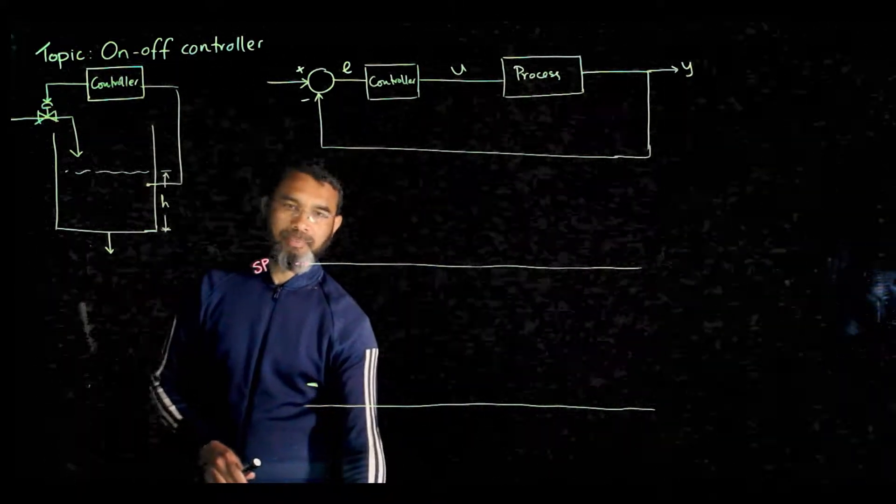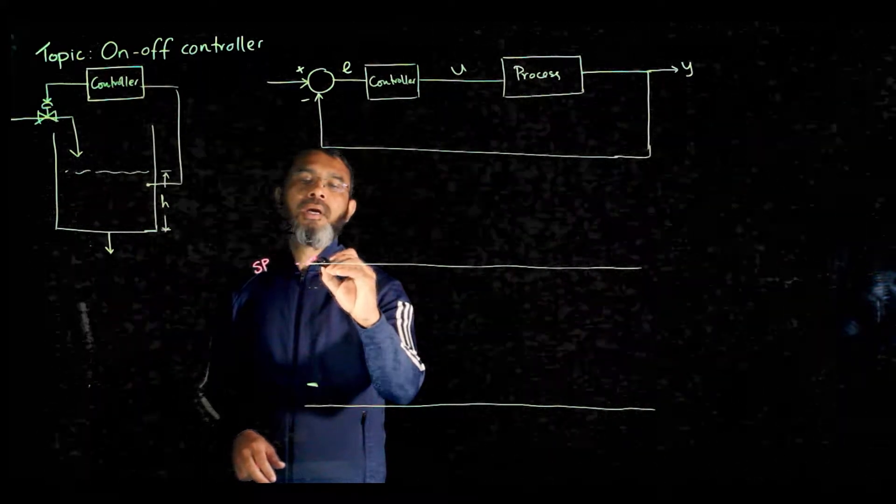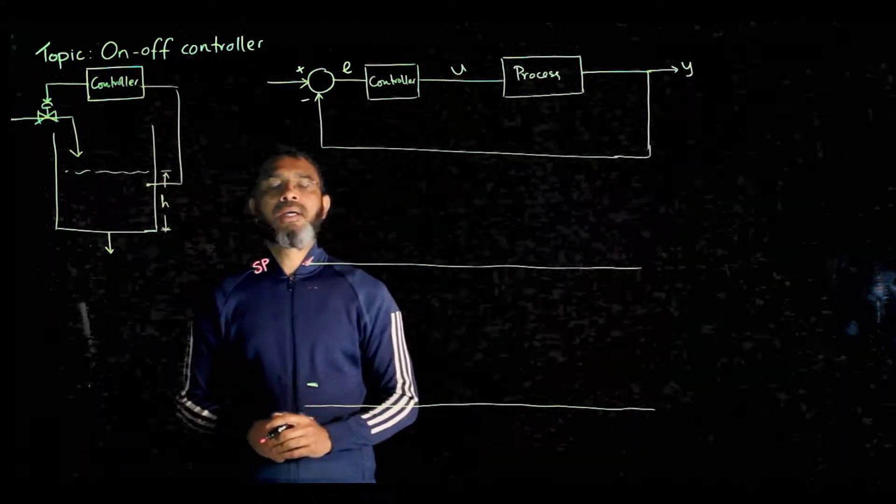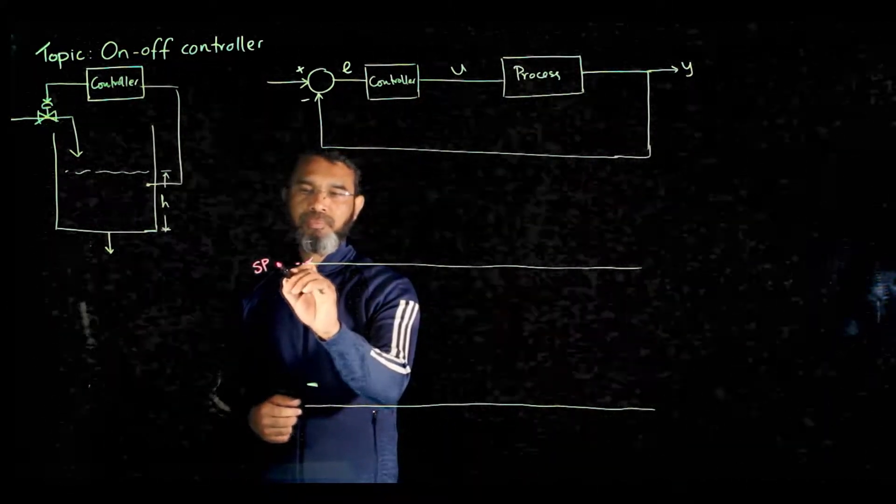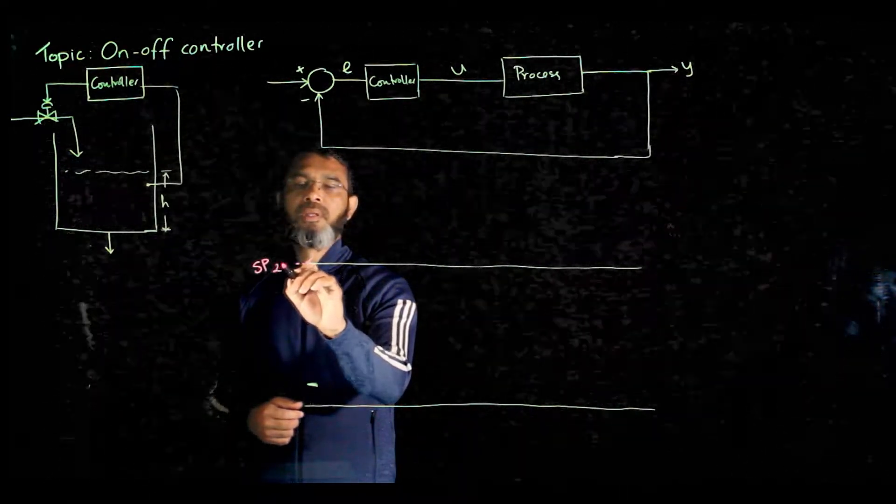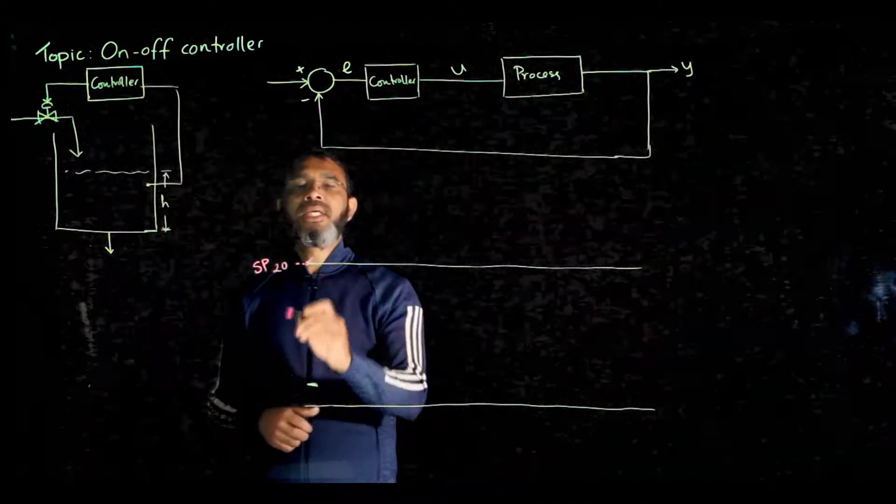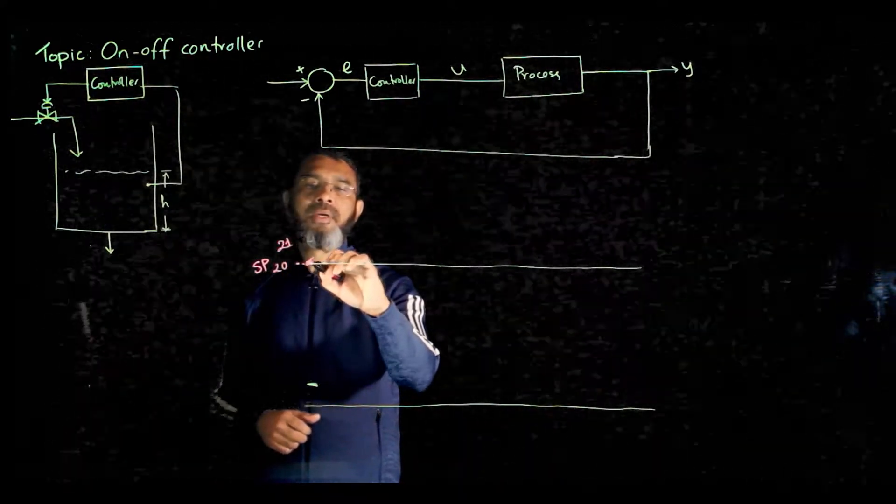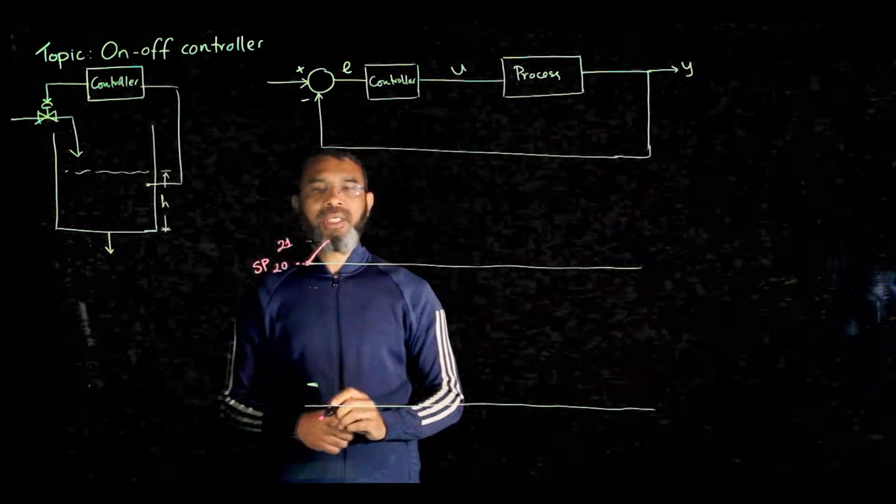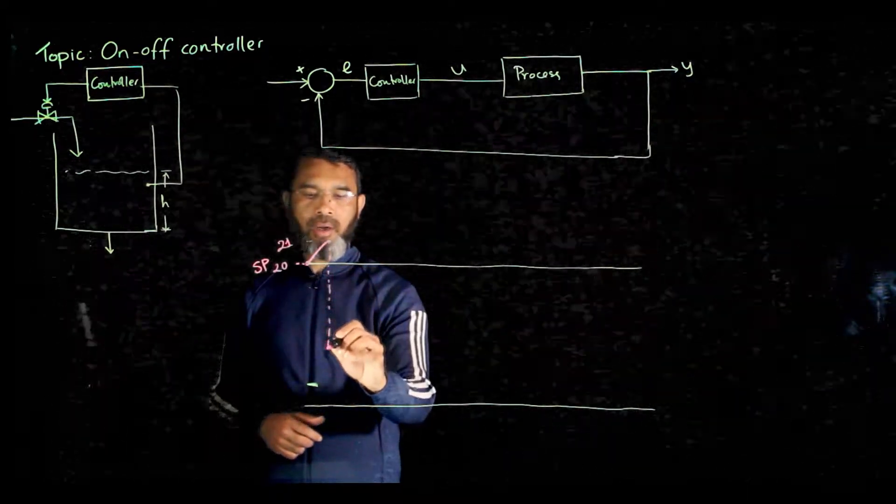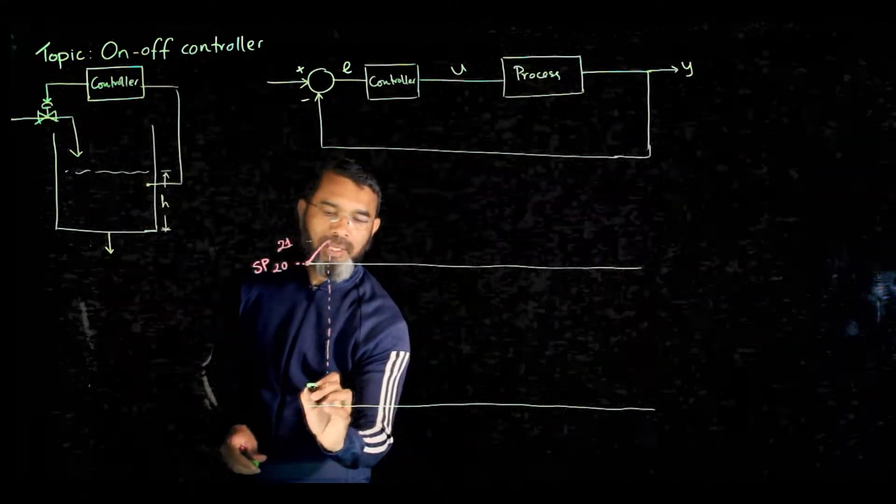Now when the valve is open, the level will keep on rising. When do you want the valve to be closed? Suppose you have a setting here at 20 units, and you may have some tolerance that when it goes to 21 units you want to close the valve. So the level will go up like this and at this point you want the valve to turn off because the level has crossed the desired value. When the valve turns off, the level will start to drop.